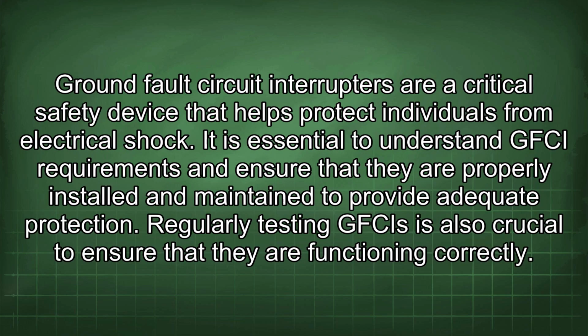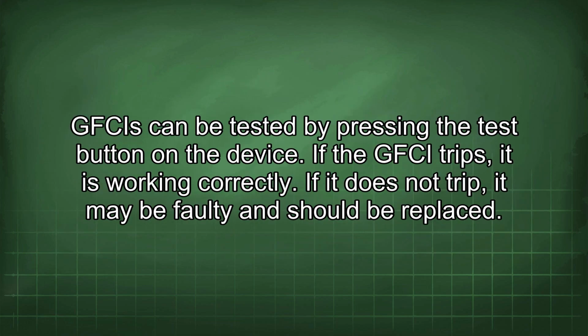Ground fault circuit interrupters are a critical safety device that helps protect individuals from electrical shock. It is essential to understand GFCI requirements and ensure that they are properly installed and maintained to provide adequate protection. Regularly testing GFCIs is also crucial to ensure that they are functioning correctly. GFCIs can be tested by pressing the test button on the device. If the GFCI trips, it is working correctly. If it does not trip, it may be faulty and should be replaced.